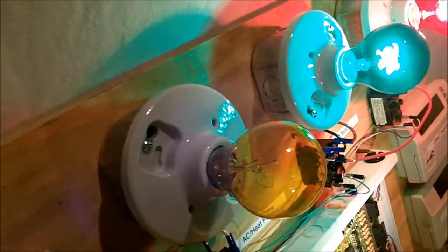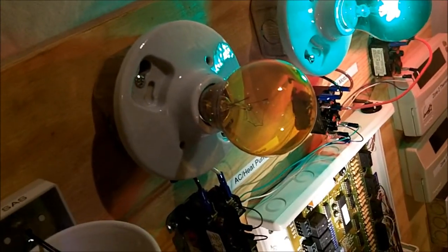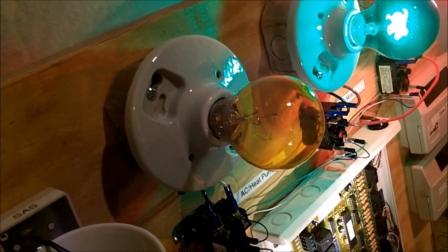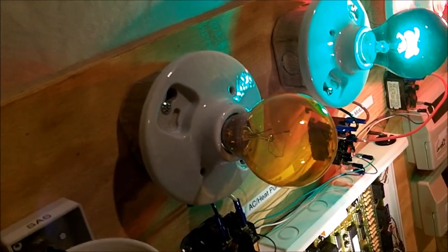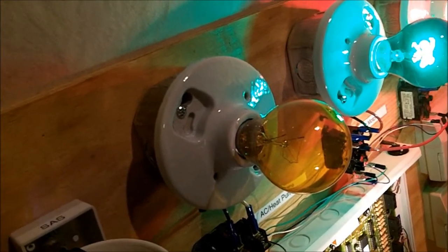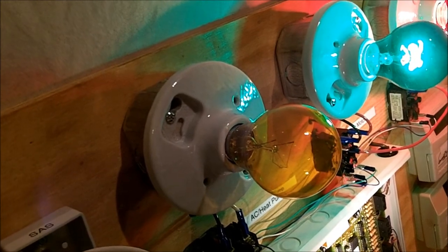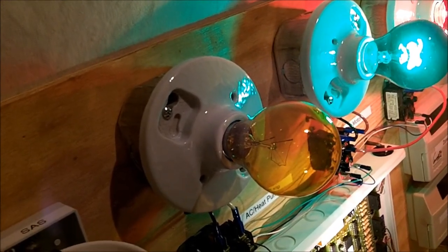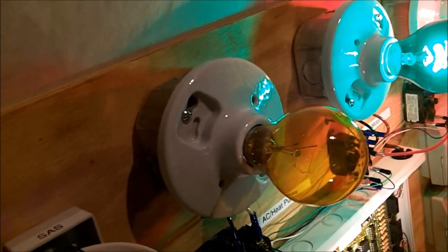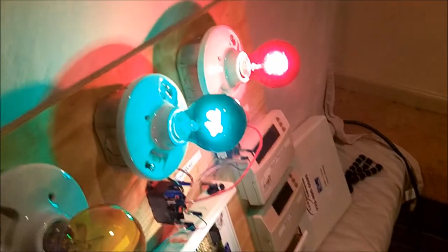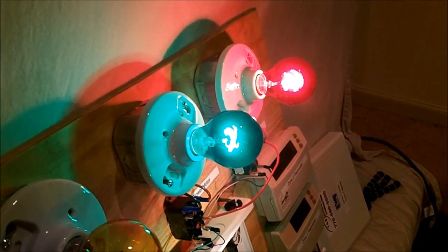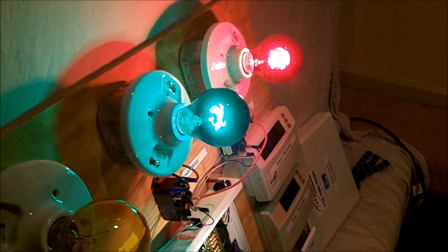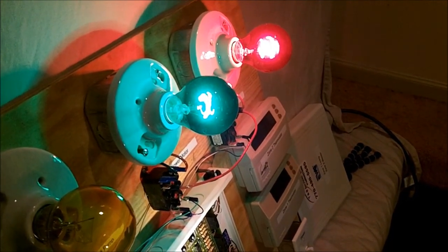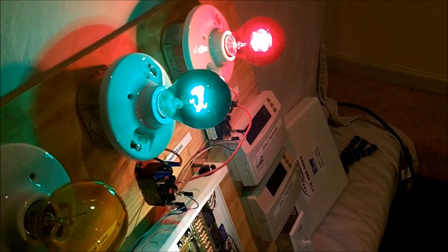Now it's going to take a minute or so, because yeah, it's 180 degrees, but keep in mind that if it's in a furnace, it's gradually getting up to the temperature. So the supply air sensor is following the temperature rise when the furnace is running. This is kind of starting off at 67 degrees. So it's going to take just a little bit to get it to turn the furnace off. And while I'm waiting on it to cool back down, what we'll talk about is the dials, the settings for the outdoor sensor, settings for the limits, staging, and okay, now the furnace just went off.